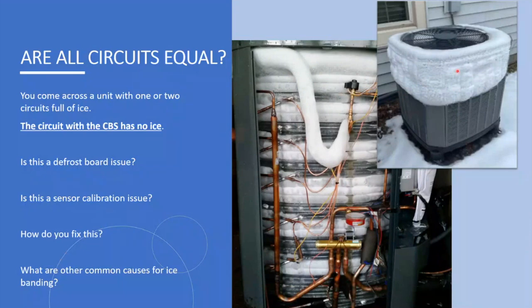So in this case here, the top is frosted, but the bottom is not frosted. So we know, here's our coil base sensor right here, and you can see that that's only on the bottom coil circuit. So it's not measuring anything on this coil from here up. So with this being frosted up, but this not being frosted up, the defrost board thinks that the coil is frost free because the bottom is.